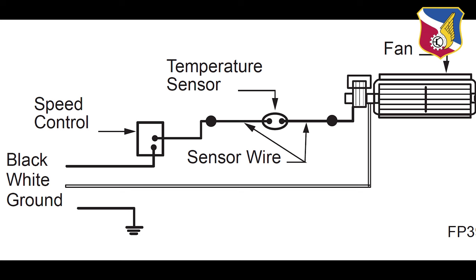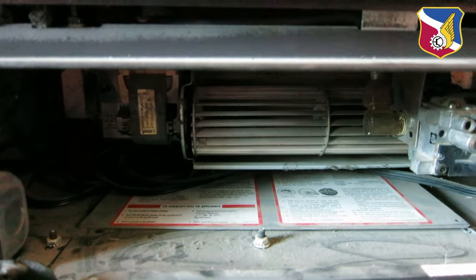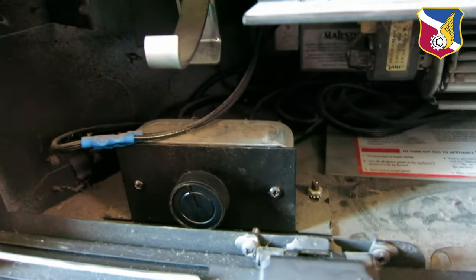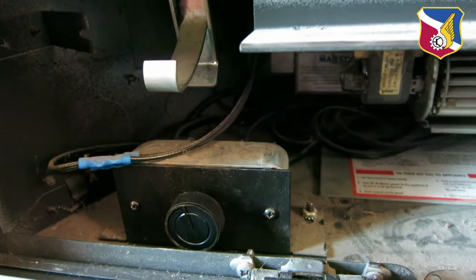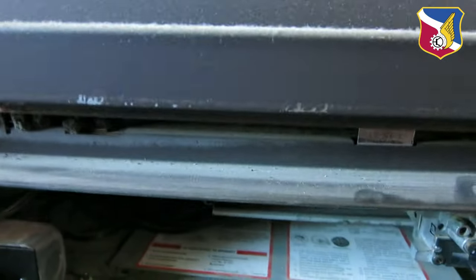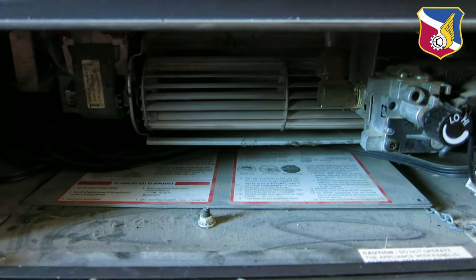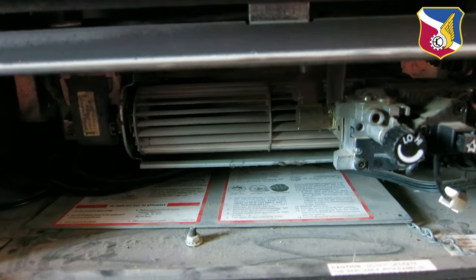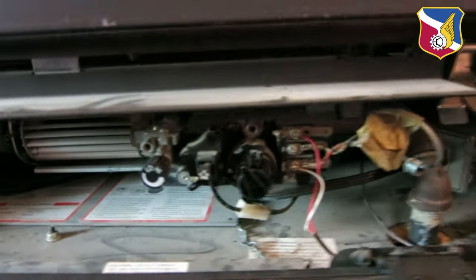So if the motor doesn't come on after, let's say 10 minutes, that's what the instructions say, then either the motor is bad, you don't have electricity coming in, the control speed control is bad, or the thermal sensor is bad. Most likely if you do have power, most likely it should be either the thermal sensor or the electric motor. So for this scenario, this is what's going on.